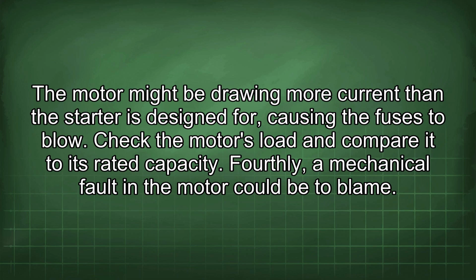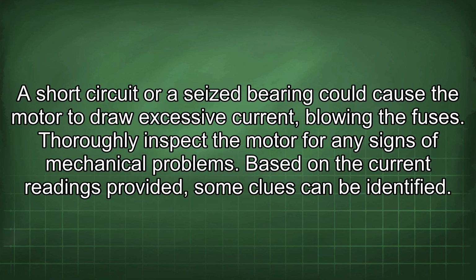The motor might be drawing more current than the starter is designed for, causing the fuses to blow. Check the motor's load and compare it to its rated capacity. Fourthly, a mechanical fault in the motor could be to blame. A short circuit or a seized bearing could cause the motor to draw excessive current, blowing the fuses. Thoroughly inspect the motor for any signs of mechanical problems.